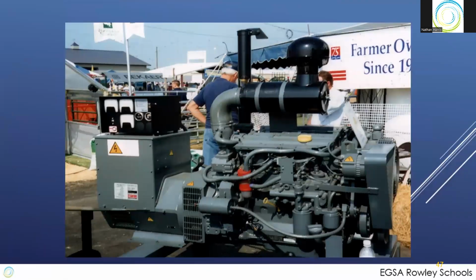Compare that with the chicken farmer generator, a little 20 kW unit. Somebody said this was a gas or a diesel. I guess I don't know what it was. But anyhow, it's very simple controls on this. The vernacular is a Murphy box, made by Murphy out of Oklahoma, but they made thousands of these things. You've got voltage, amps, and frequency meters. You've got an hour meter, an oil pressure gauge, and then either a key switch or toggle switch, I can't tell. But anyway, very, very simple controls. Obviously, the engine ECU will do the engine protection, and the generator output breaker will do electrical protection. That's really about it. Right? So the level of controls is much different here.